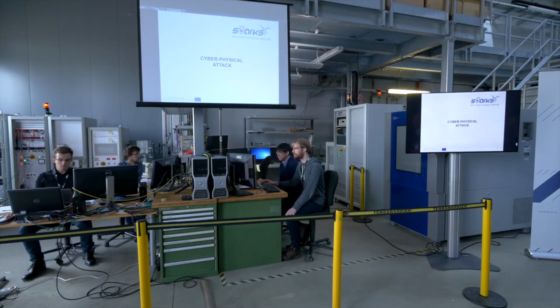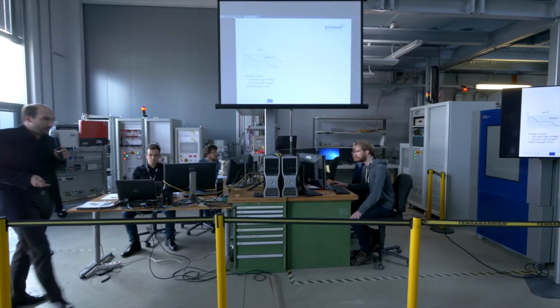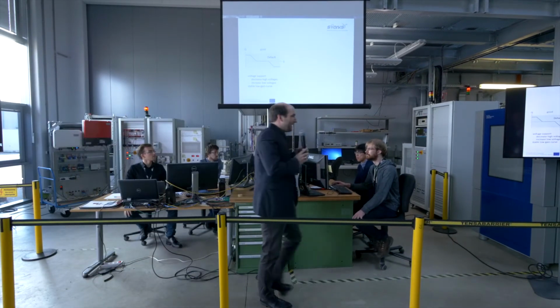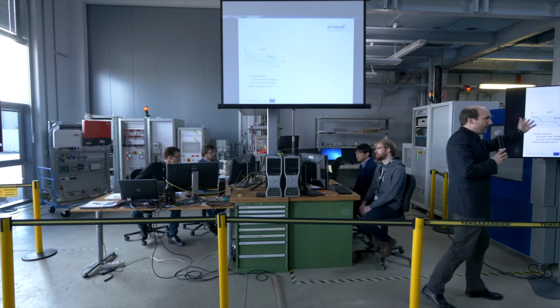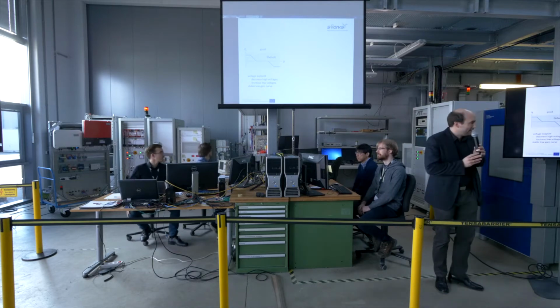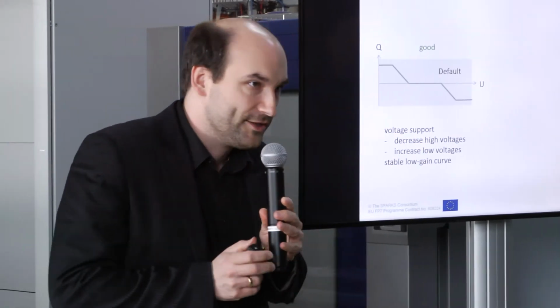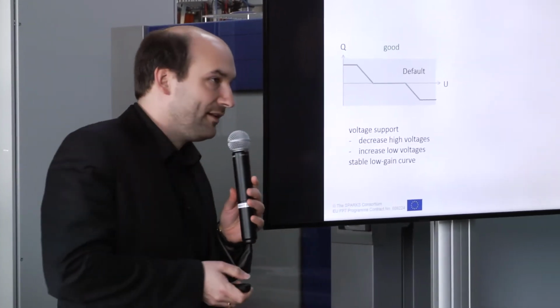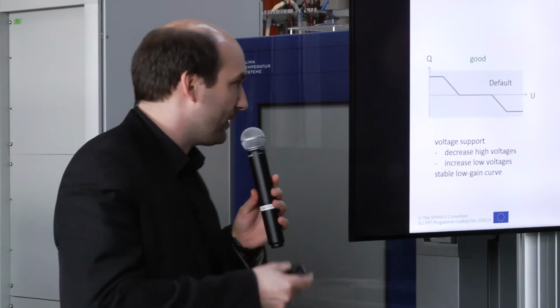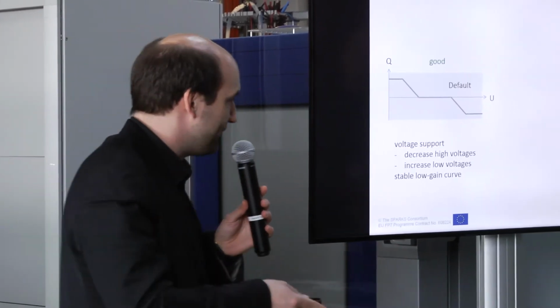Right, so what are we going to do? We are fiddling around with this reactive power curve. In the normal setting, as you've seen it here, it actually supports the voltage. So when the voltage goes higher, reactive power is taken from the grid to damp this effect, and vice versa.